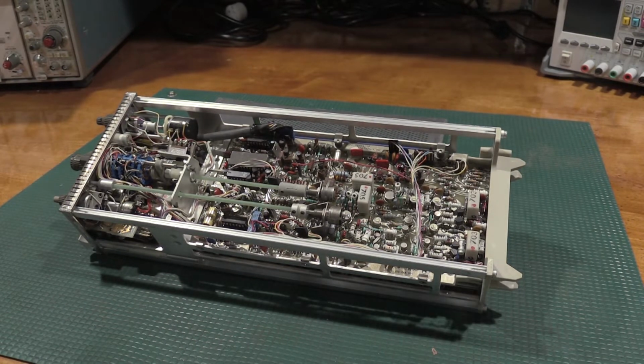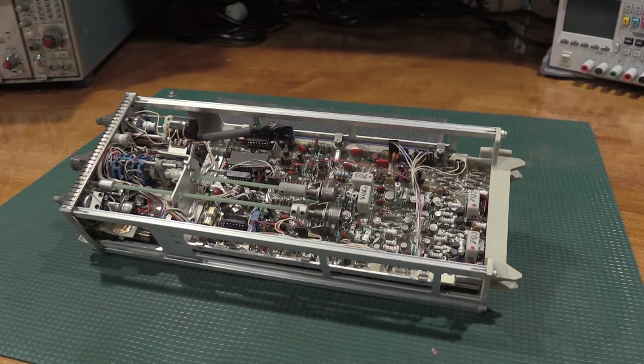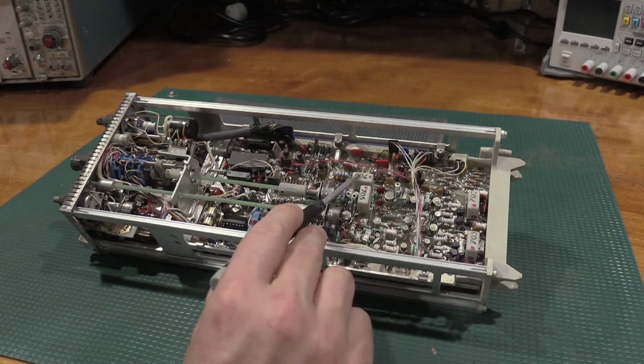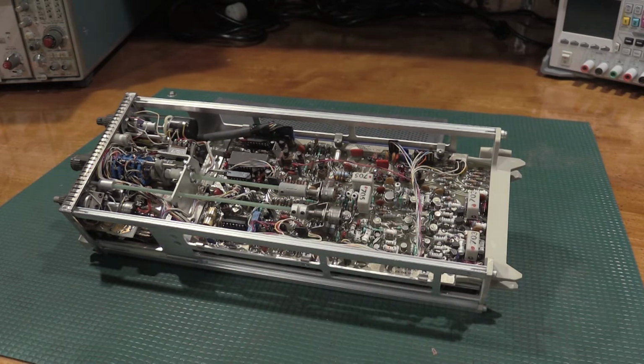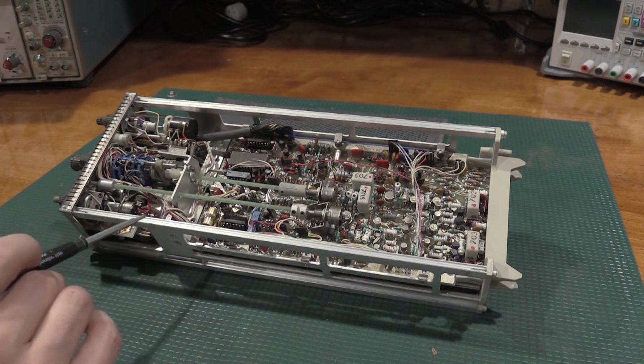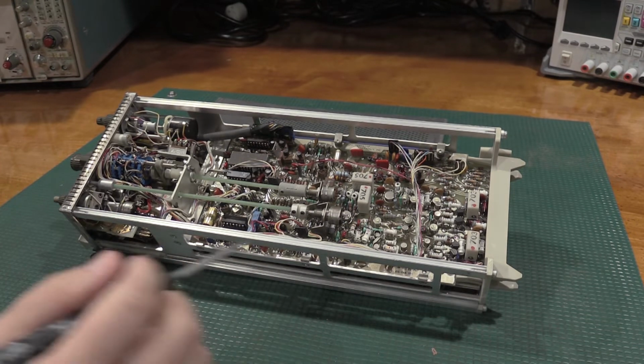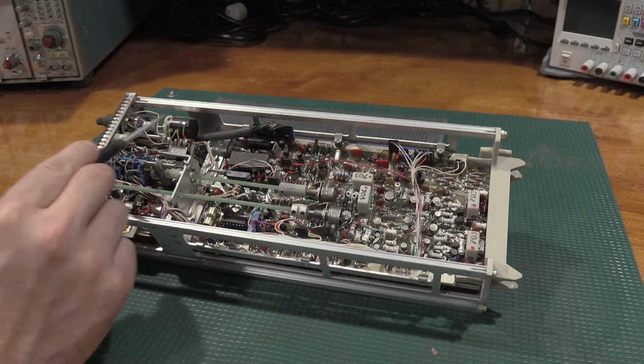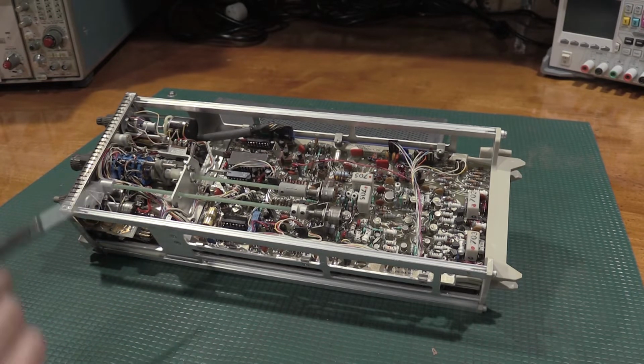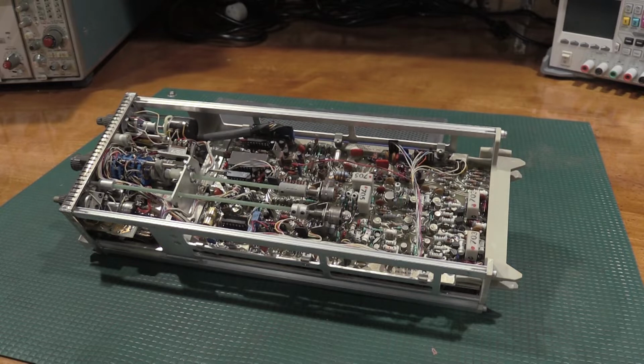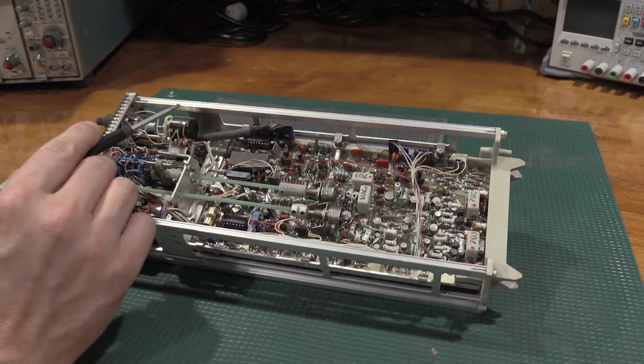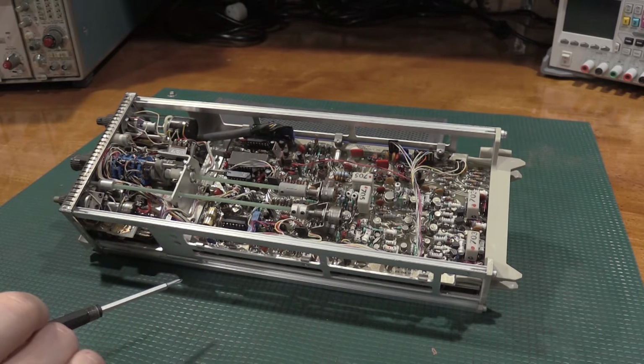I just took the right-hand side cover off. Some of the problems to be aware of in this particular unit are these micro relays. When these things start having problems, they can be challenging at best to source and bordering on unobtainium. There's two versions of the 7A15 or the 7A13. One has a mechanical section up in here, and it uses plastic gears in that mechanical section. That does not age well. So if you can get the digital version, that is definitely preferred.